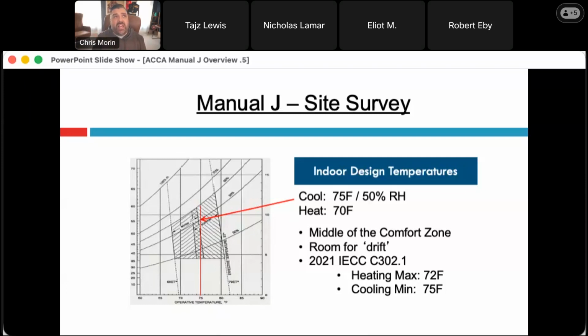So if it is, let's say, 110 degrees outside and the system can't keep up sensible temperature wise, we're going to continue to run the system and remove moisture. And it might be 77 or 78 degrees inside, but 40% relative humidity because the system's been running all day, and we're still within that comfort zone. That's an extreme situation. In the mild situation, when the system is oversized and it short cycles a little bit, it might be 73 or 72 or even as cold as 70, but it might be 55% relative humidity inside, and we're still within that shaded area and we're comfortable.